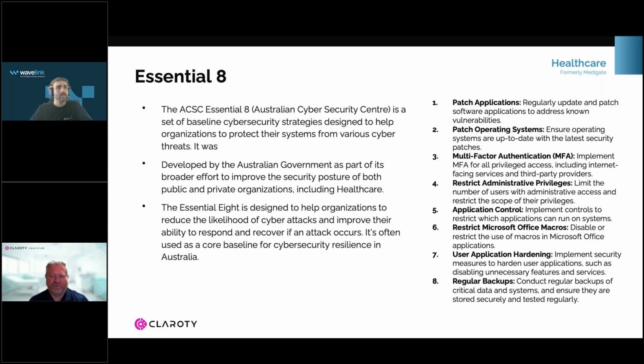And with restrictive admin controls, from an OT perspective, we always look at it as what we call ZTNA, so zero trust or lowest privilege. So what is the absolute minimum privilege that we need to apply to an asset that lets it function, lets it do what it's supposed to do, but alleviates the risk of having people with too much access being able to jump onto that asset or device and make changes either to configuration files, to parameters around the device asset, how it's being used, and those sort of things. So we look at that.